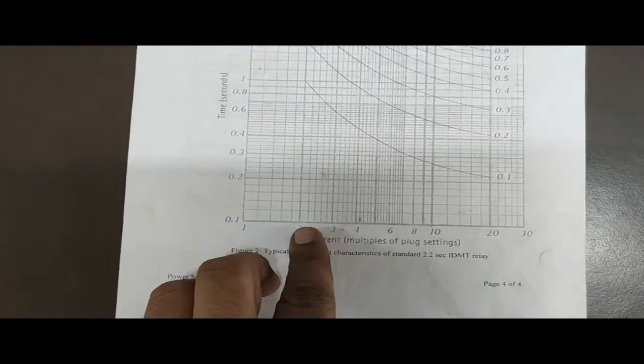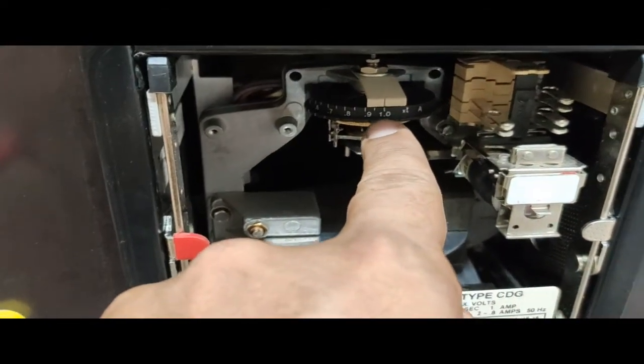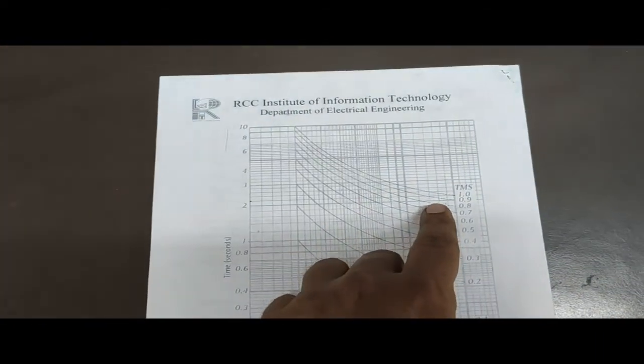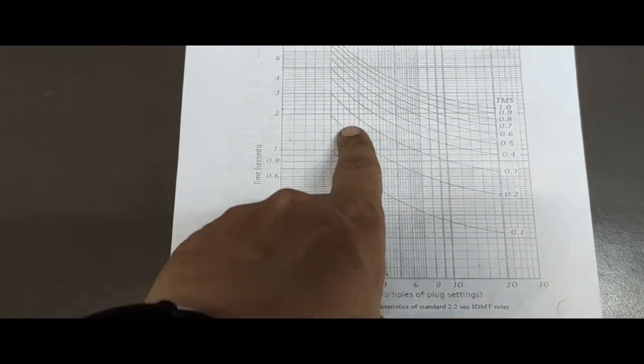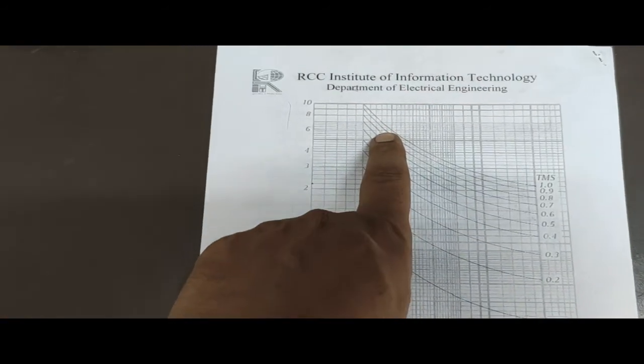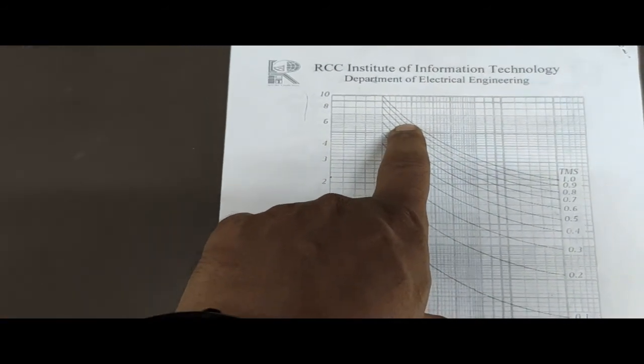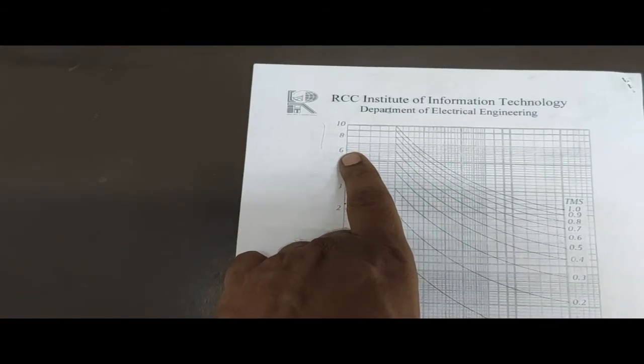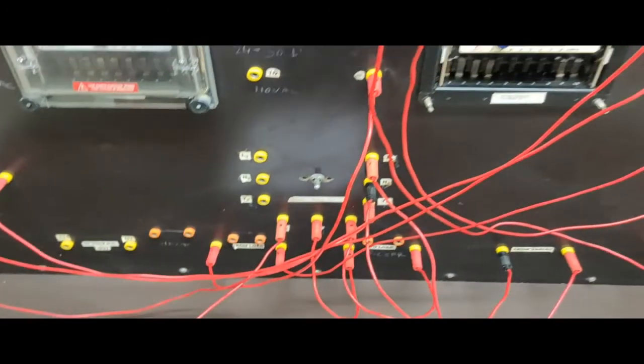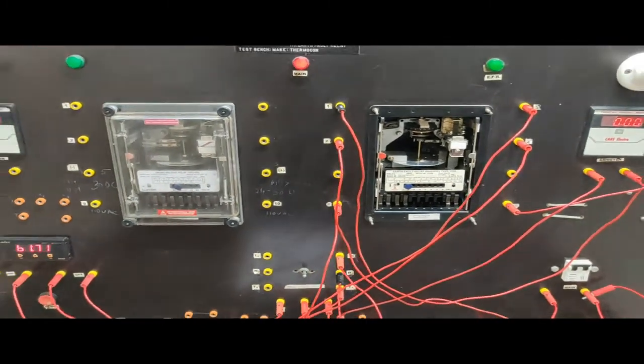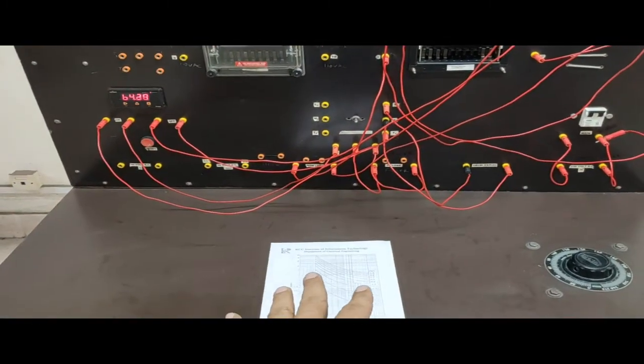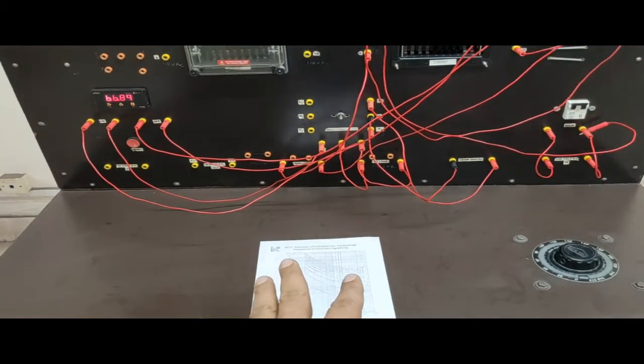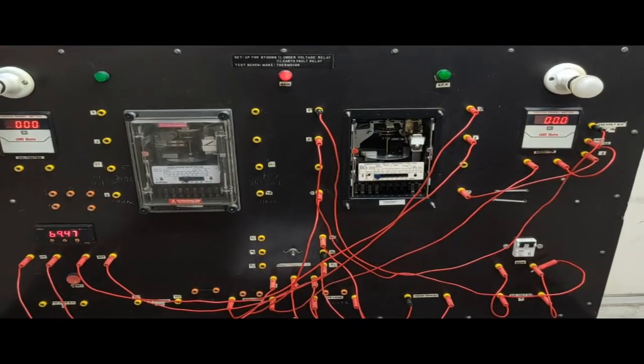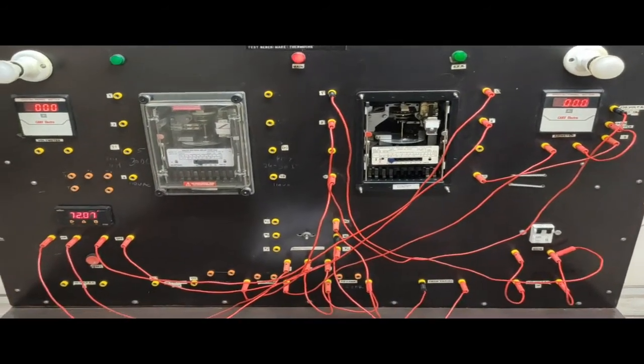So now come to this one. So this is the plug setting multiplier 3 and the time setting multiplier is set at 1.0. So that means here first we need to follow the first curve. Okay, and this is the intersection of the first curve and the plug setting multiplier 3, and according to this one 6.2 will be the time required to operate the relay. Okay, now let's see how much the relay is actually giving. That is the theoretical value which we get from the IDMT characteristics curve, but practically how much time the relay will take to generate the trip signal we need to measure.